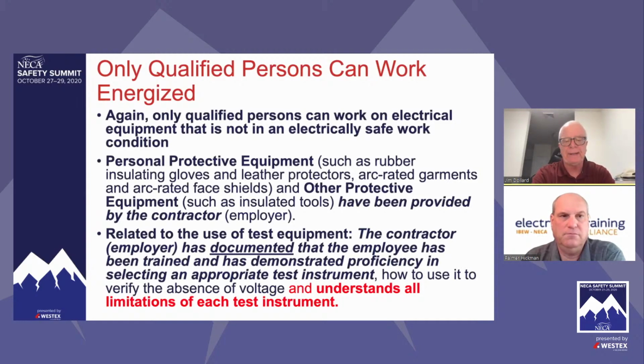It's easy for us to make mistakes here. We have to train everyone that is going to use test equipment on a job, and 70E uses that term, test equipment. And why don't we just say voltage tester? Because it has to include an amp probe. It has to include a phase rotation meter. There's so many different things that we use, but the employer has to document that the qualified person has been trained on the use of that test instrument. So if everybody's got their own test instrument, I don't know how we're going to get that done.